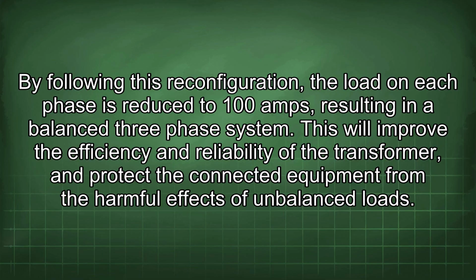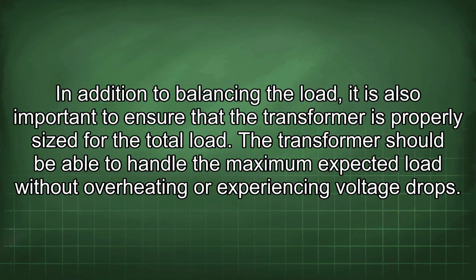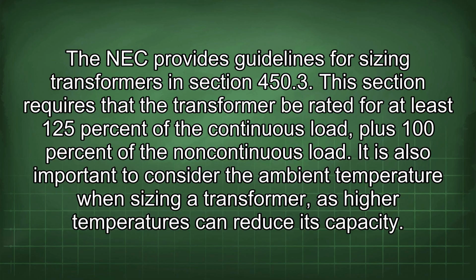This will improve the efficiency and reliability of the transformer and protect the connected equipment from the harmful effects of unbalanced loads. In addition to balancing the load, it is also important to ensure that the transformer is properly sized for the total load. The transformer should be able to handle the maximum expected load without overheating or experiencing voltage drops. The NEC provides guidelines for sizing transformers in section 450.3. This section requires that the transformer be rated for at least 125% of the continuous load, plus 100% of the non-continuous load. It is also important to consider the ambient temperature when sizing a transformer, as higher temperatures can reduce its capacity.